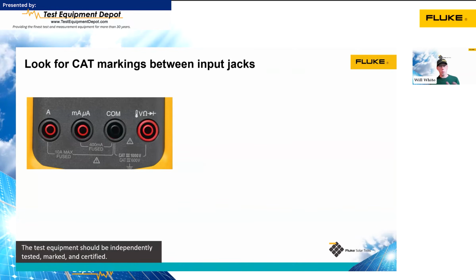So how do I know what my meter is rated for? If it's a new meter, it's going to be marked right on the meter. All Fluke meters have them printed right on the front of the meter. This is a multimeter rated for category 3 1000 volts and category 4 600 volts. It's very common to have a higher voltage rating at a lower category. And so this category 3 1000 volts, category 4 600 volts is very common. The 393 clamp meter is 1500 volts, category 3, 600 volts, category 4.